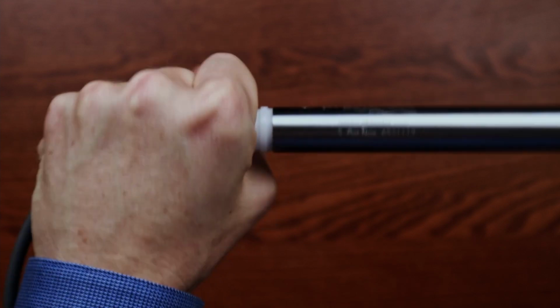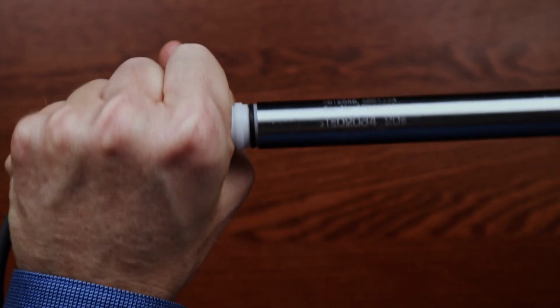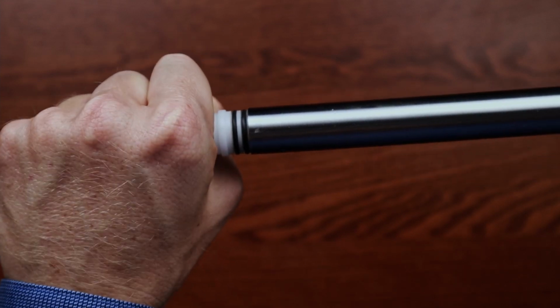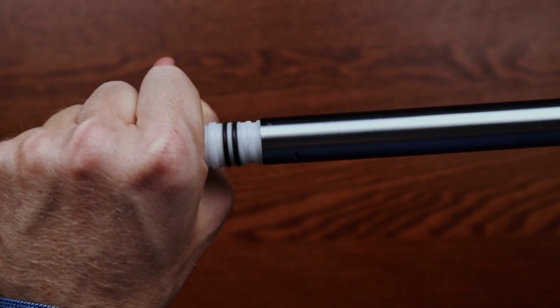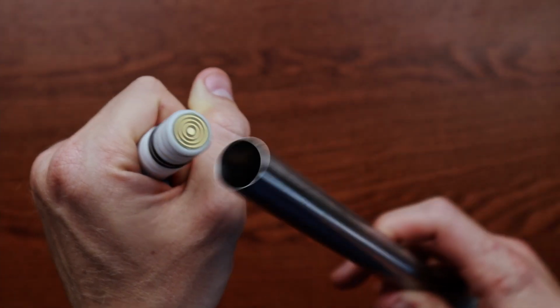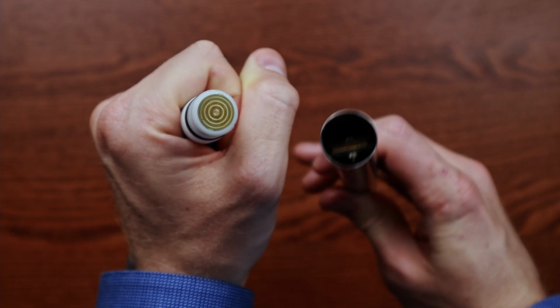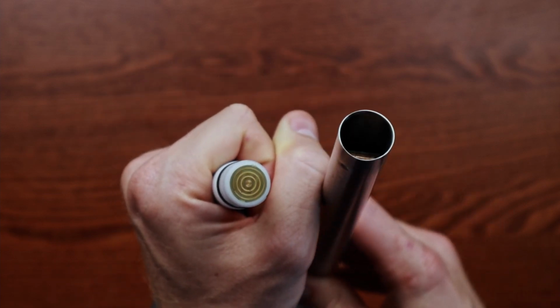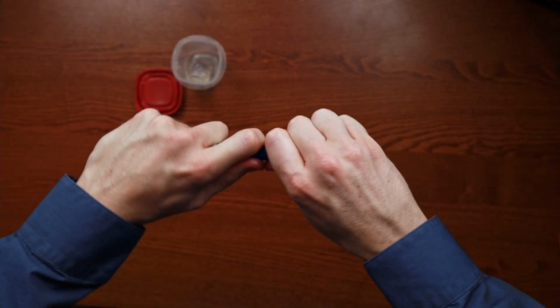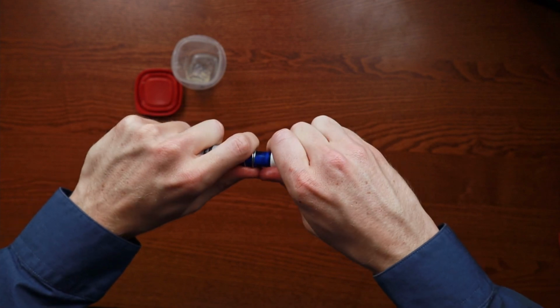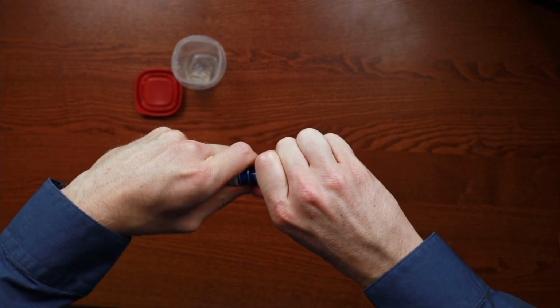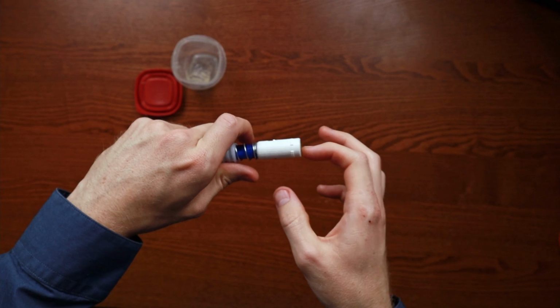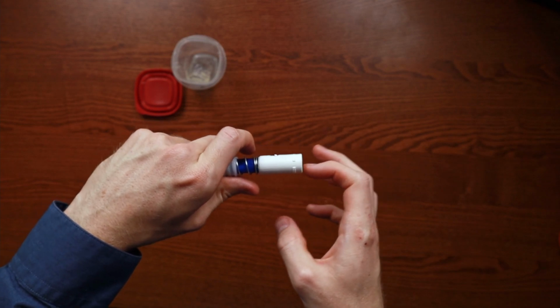When opening the sensor, it is important to check if any moisture is present or if there's discoloration on the connectors, as that would indicate corrosion is occurring. Water could enter due to an ungreased or old or damaged O-ring, or from trapped water during previous maintenance. Lastly, whenever the electrode is removed, it must be reinserted at the proper depth to contact the circuit board. This depth is indicated when the depressed electrode cap barely touches the spring.